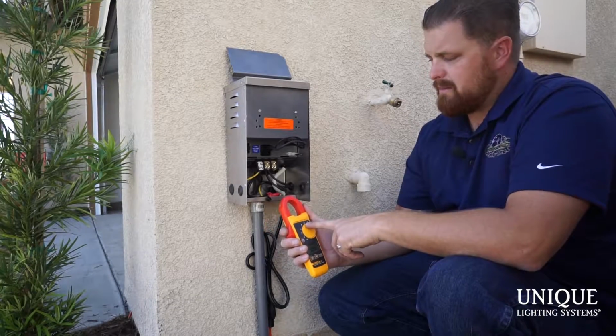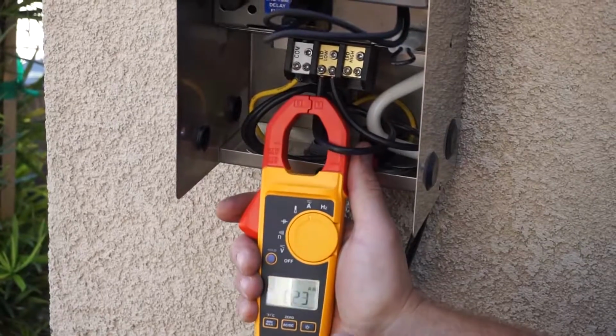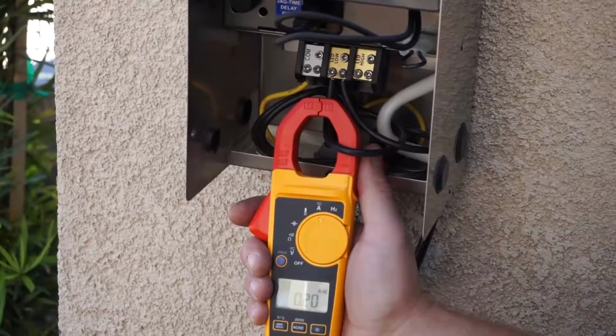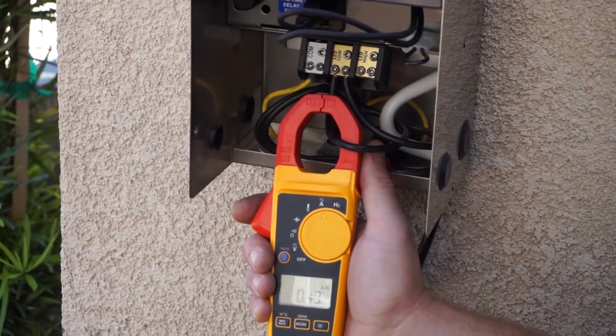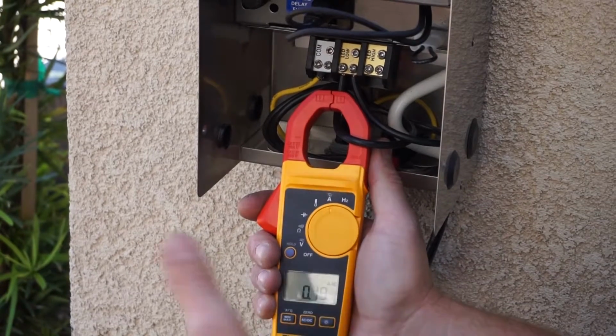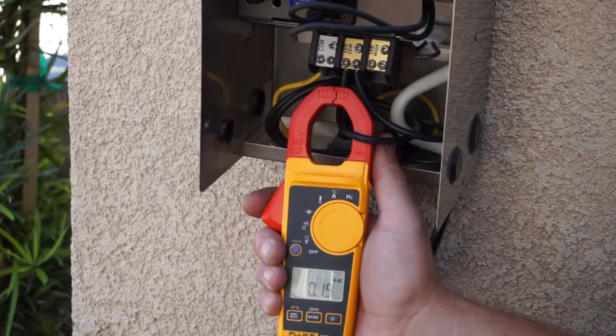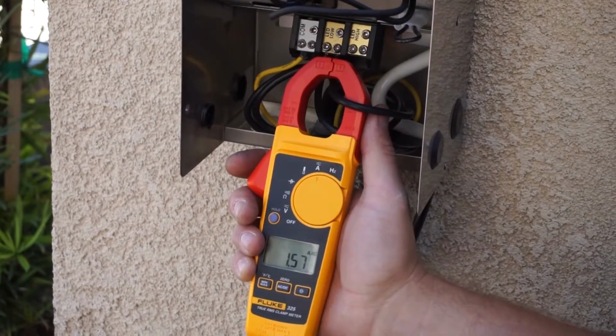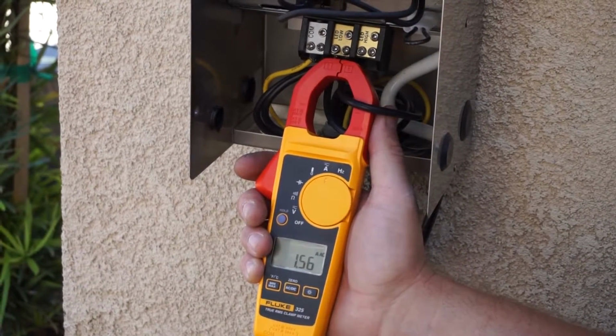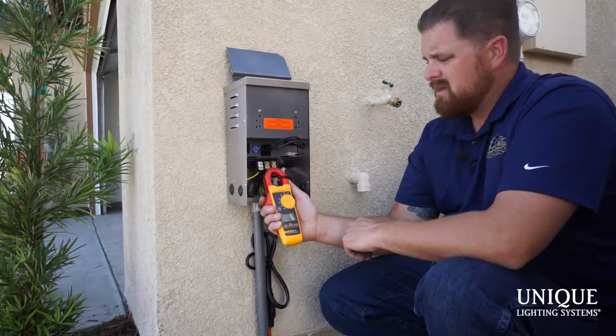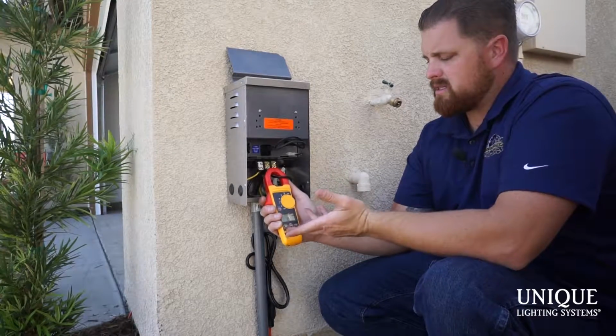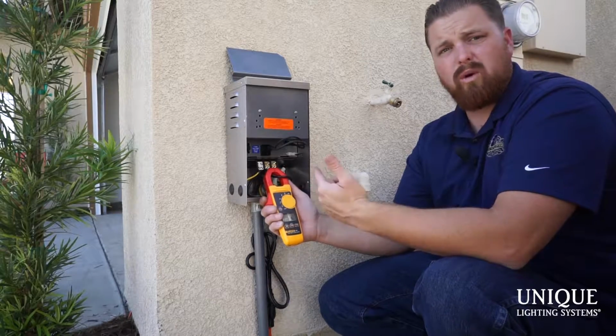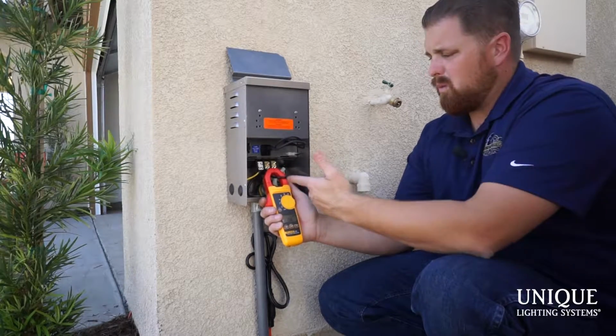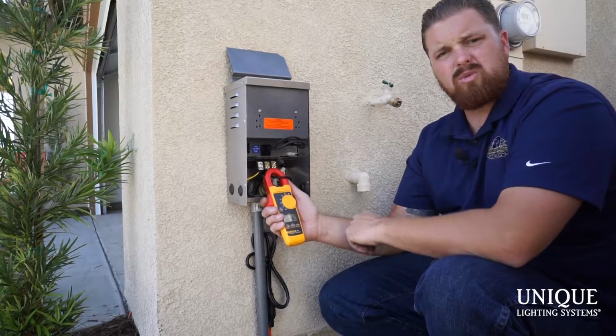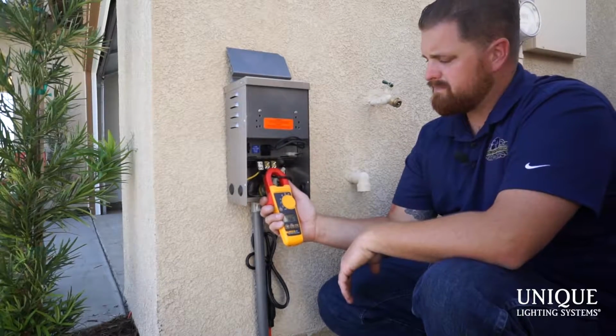So again, leave it on the amperage setting and you're just going to check one of the home runs. I'm at 0.20 amps. And you see it's still dropping, zeroing in right now. So 0.19 amps, way under my 16 amp max. And then I'm going to check the second home run. And I'm at 1.56 amps, so again, way under my 16 amps. So looking at this, obviously I could have probably put all these fixtures on one home run, but one transformer home run wire is going to the backyard, one's going to the front yard, so we just have it separated out for future expansion.